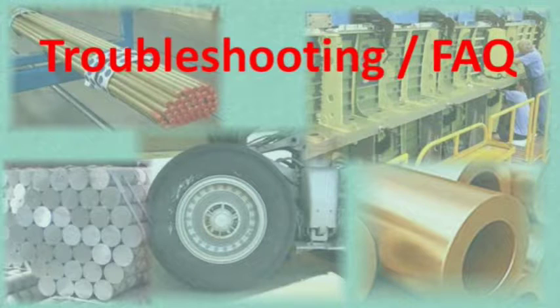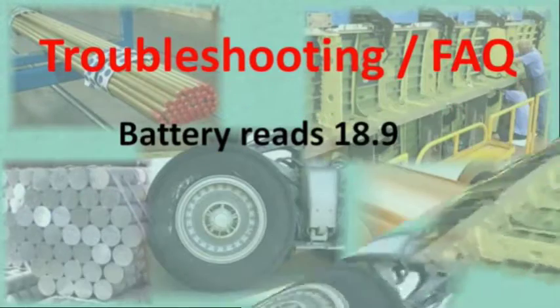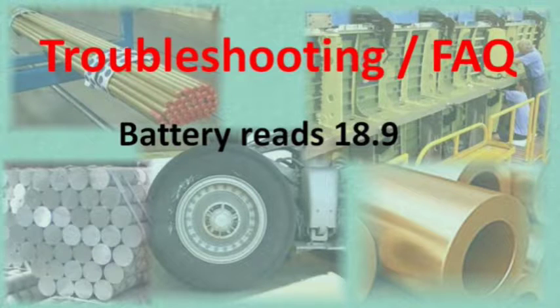Now that the instrument is up and running, it is designed to perform accurately and reliably for a long time. However, there may be instances where the instrument may not appear to be working properly. I will address the more common questions our customers have posed to us in the past. The first is regarding an 18.9 reading when the battery push button is pushed. This means that there is an issue with the batteries. 18.9 means that there is insufficient charge to operate the instrument. Charge the unit overnight and test again. If the reading is still 18.9, then the batteries will have to be replaced because they will no longer accept a charge.